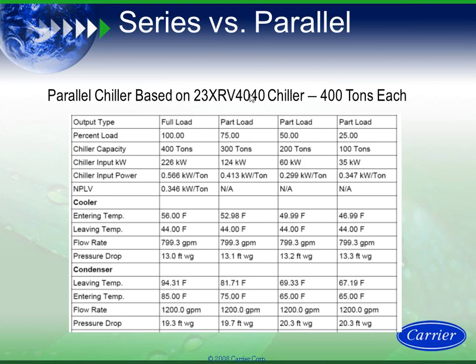So let's look at a 23XRV 4040 chiller. The 4040 dictates the amount of copper that's in those cooler and condenser shells, each at 400 tons. So in this case, I am running 400 tons at 0.566 full load and 0.346 part load on this chiller. 44, 56, 85, 3 GPM per ton on the condenser.